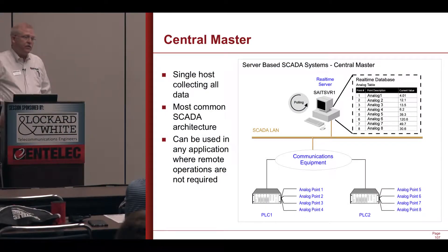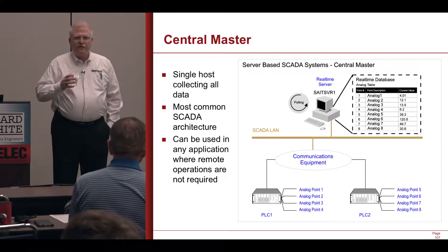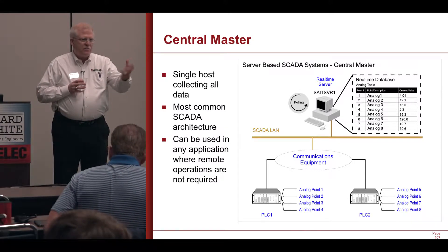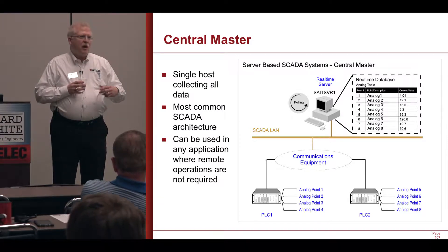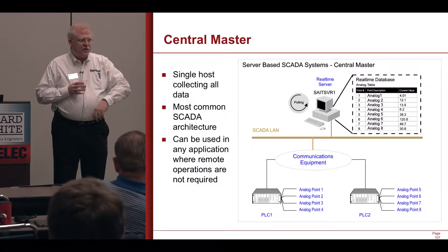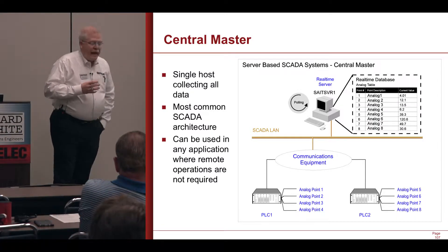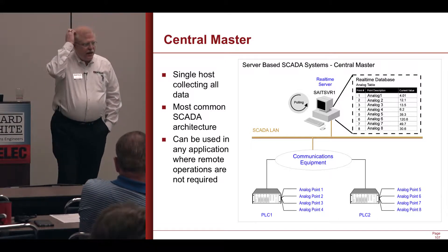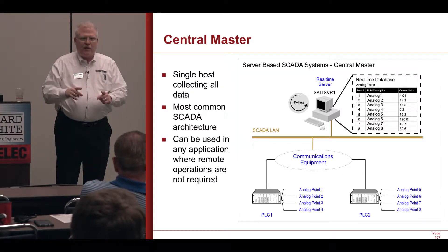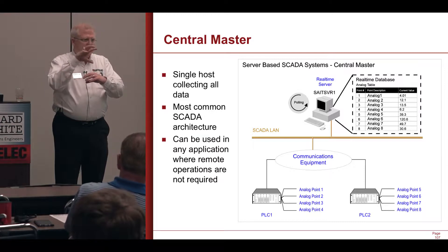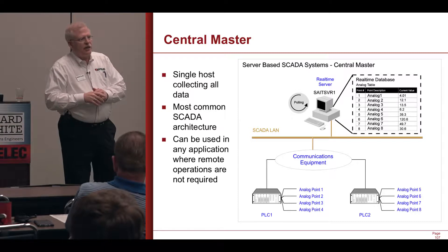All SCADA systems are client-server. The polling engine is the server. The client, the HMI, asks the polling engine for data and the polling engine goes out and gets it if it's a demand request. Otherwise the polling server is asking for the data and bringing it up and storing it in the HMI. At its very simplest level, all SCADA systems are what we would call a central master — meaning one polling server and one HMI package sitting on top of it. Could be more than one console, but one polling server. So that would be a central master.